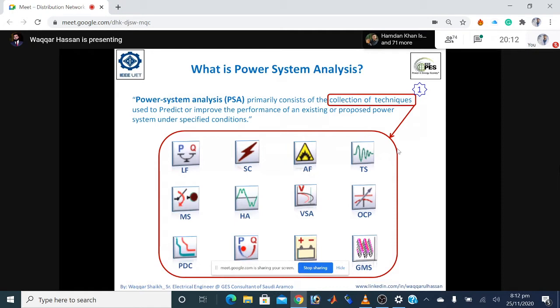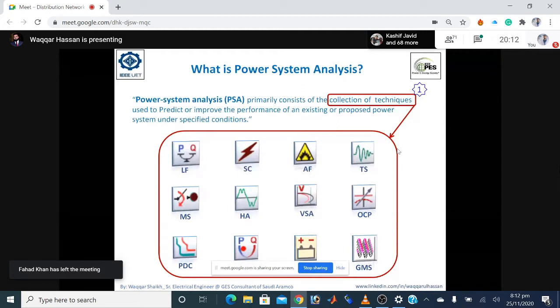Similarly, the other type of study can be fault analysis or short circuit analysis. This is the second most important study required to be conducted. It enables power system engineers to decide about the thermal and electrodynamic withstand capabilities of electrical equipment, such as switchgear, cables, generators, or motors. All these equipments must be robust enough to face short circuit effects. So short circuit analysis considers fault scenarios where these faults can affect the equipment's health.